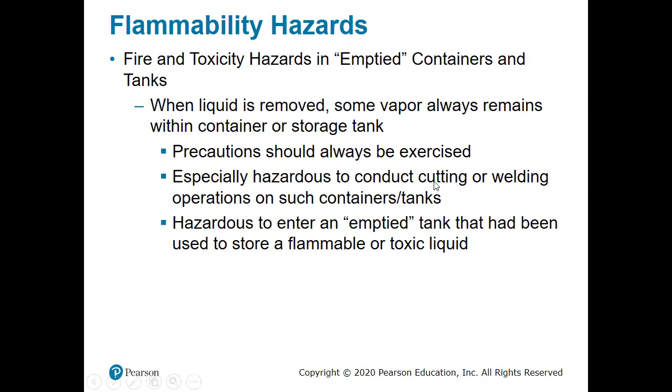So when it comes to empty containers, you've got to be careful about just cutting into them or welding into them without any kind of thought about it. You cut into a tank that was holding a flammable liquid, and now you're exposing that flammable liquid to your acetylene torch. And guess what? You've got a bomb. Because the vapor inside is all trapped.